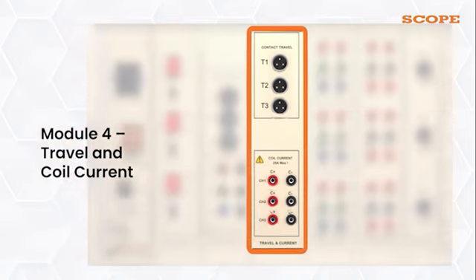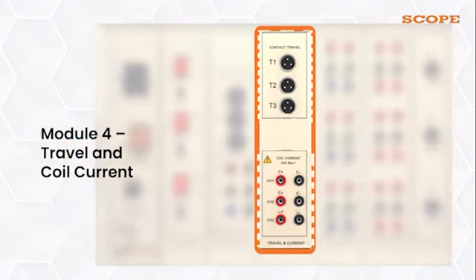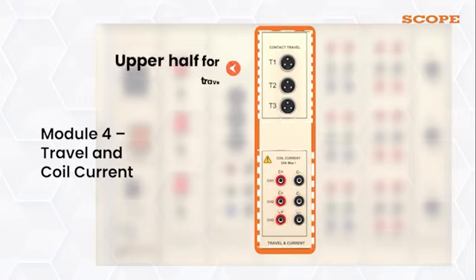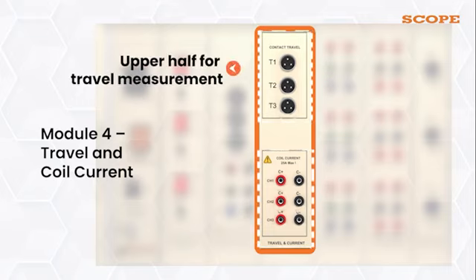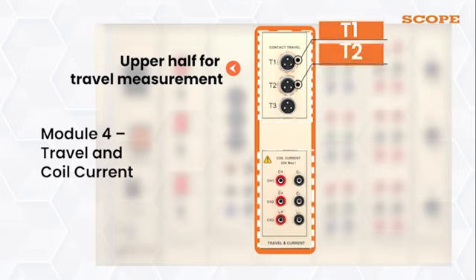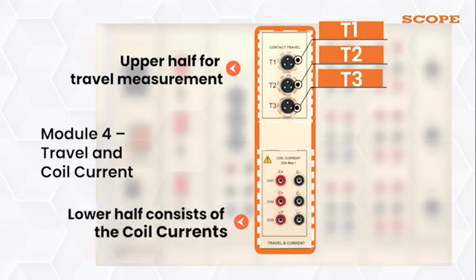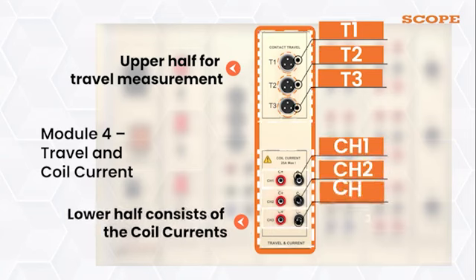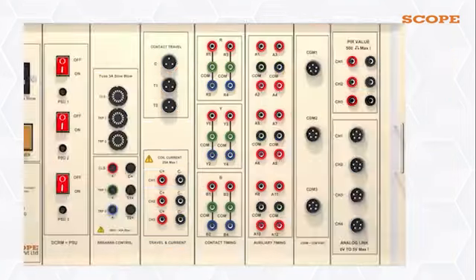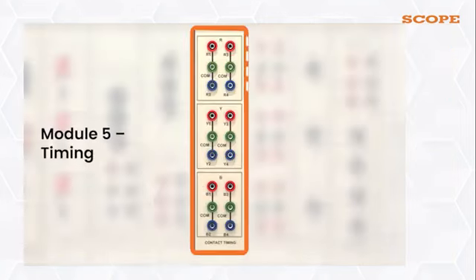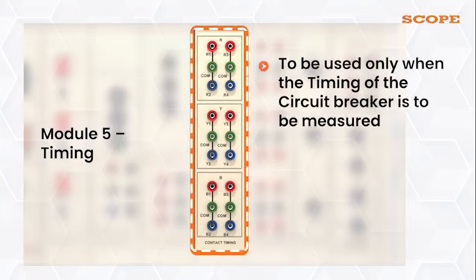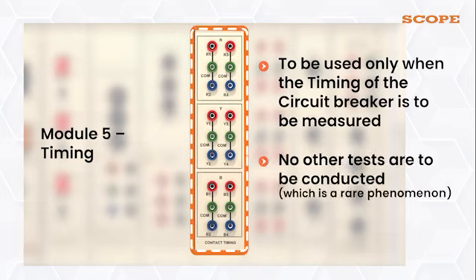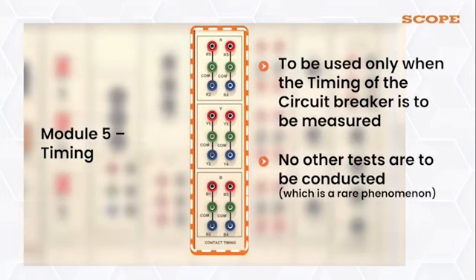If you look closely, you can understand this module is also divided into 2 halves. The upper half for travel measurement through 3 connectors T1, T2 and T3. Whereas the lower half consists of the coil currents channel 1, channel 2 and channel 3. Module 5 Timing Module. It has to be used only when the timing of the circuit breaker is to be measured and no other tests are to be conducted, which is a rare phenomena.